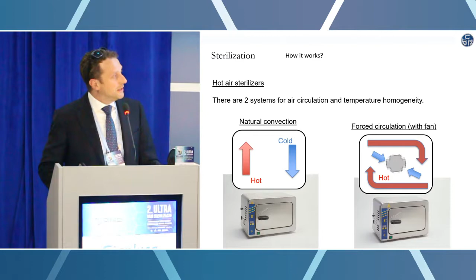Steam sterilization works with heat, but together with moisture, because, as we learned this morning, the heat contained in steam is very high. By condensing over the surface of an organism, it lets the proteins coagulate and become a new molecule that poisons every viable organism that you may have on your medical device. It works normally at 121 degrees or 134 degrees at a higher pressure.